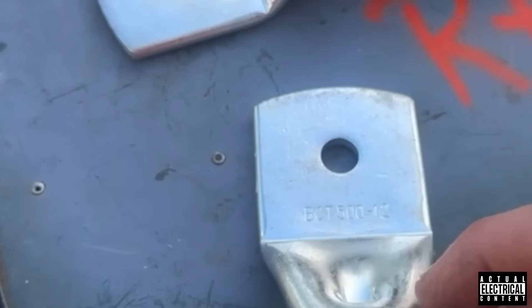The BCT will be their code, and when you look in the Cembre catalogue, you'll select the code you've got, and it'll tell you what dies to use and how many indentations to make on the lug. It'll also tell you for different size cables what things to use, because different cables require different lugs. The most important thing is you've got the right lug for the right cable, and you crimp it with the right die at the right pressure with the right amount of indentations, and you inspect it to see it's there.